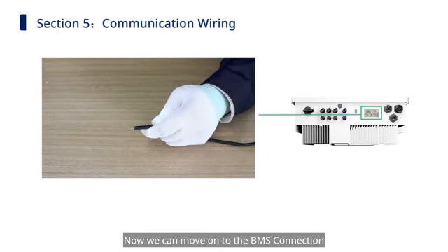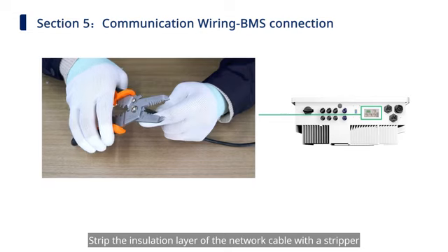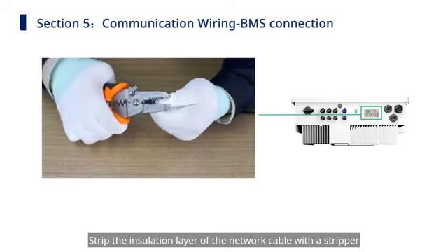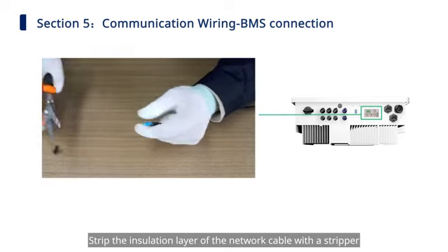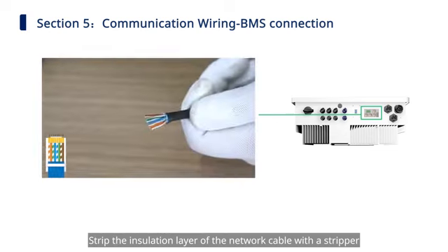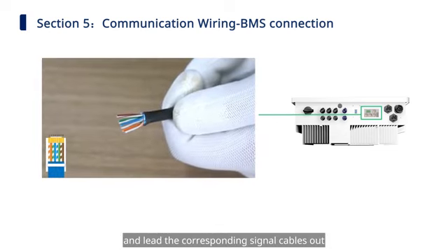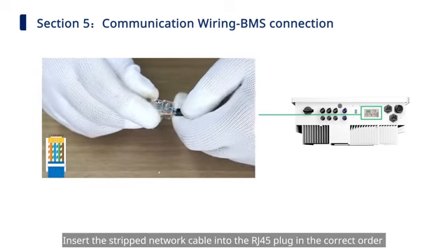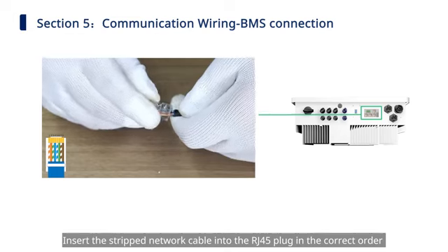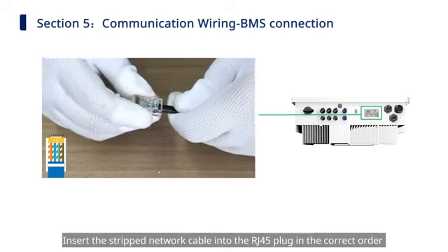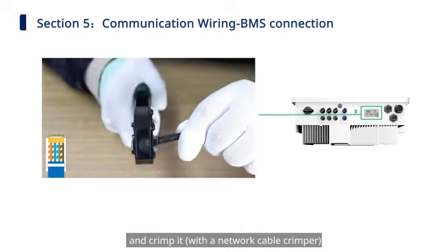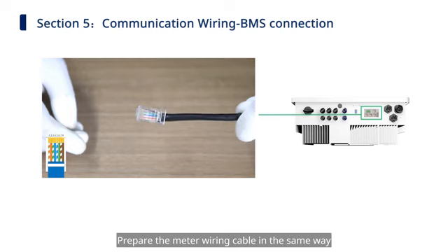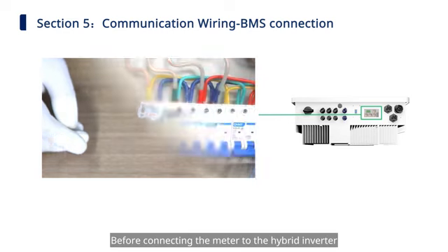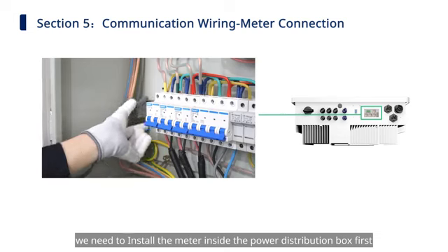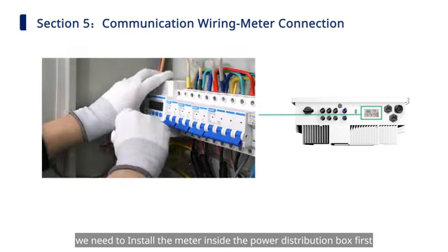Now, we can move on to the BMS connection. Strip the insulation layer of the network cable with a stripper and lead the corresponding signal cables out. Insert the stripped network cable into the RJ45 plug in the correct order and crimp it. Prepare the meter wiring cable in the same way. Before connecting the meter to the hybrid inverter, we need to install the meter inside the power distribution box first.